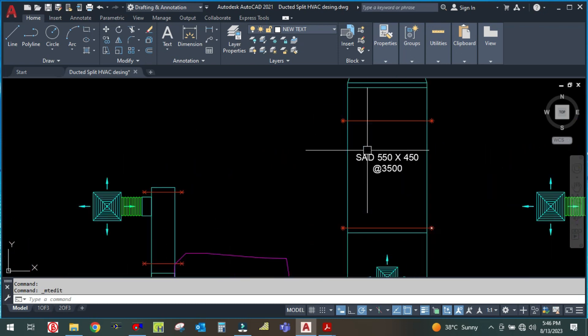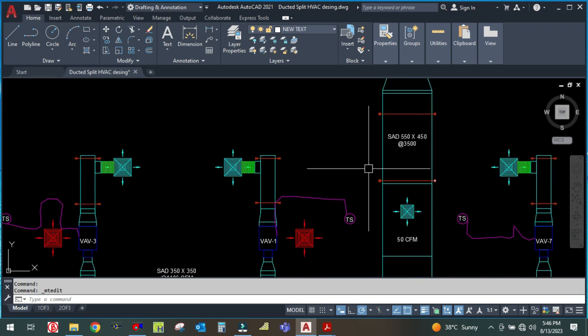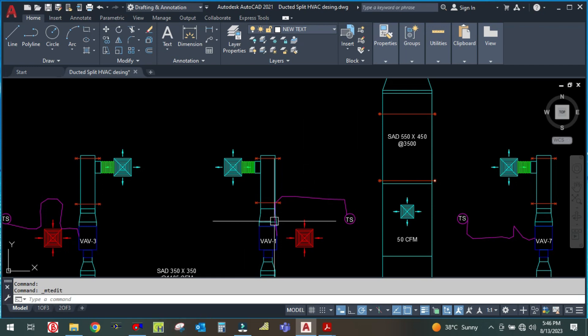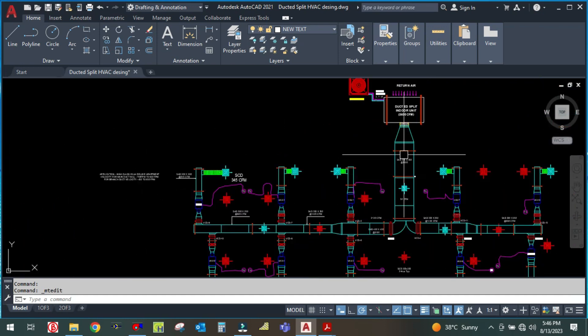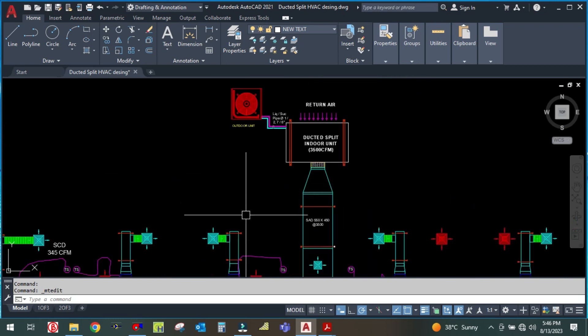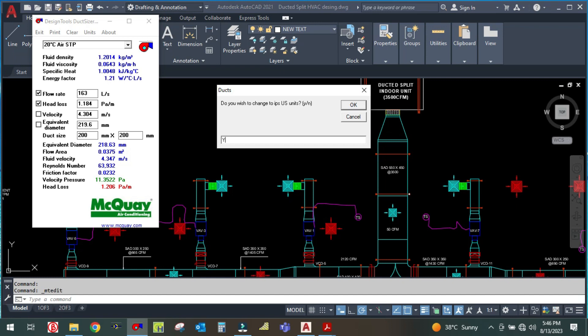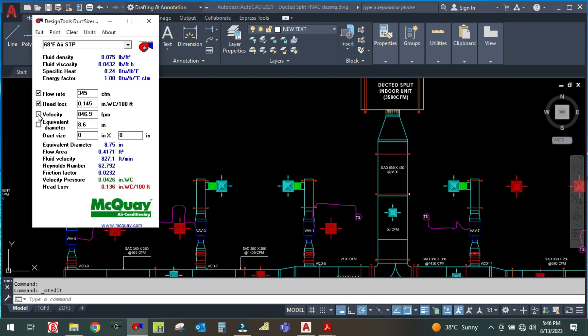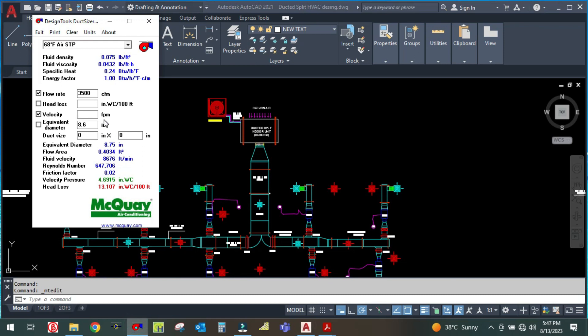The duct height will depend on the false ceiling space — the gap between the false ceiling and the slab. So let us design this. Here the CFM will be 3500. Open the duct sizer, fix the flow rate, then fix the velocity.